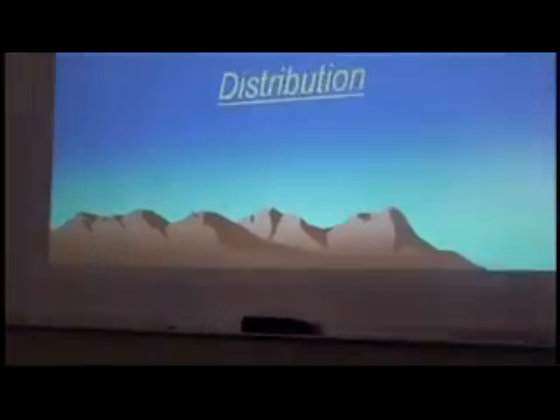This is the kind of damage they find — here's a combustor basket with the unit shut down. This is what they discovered: the metal had started getting damaged, and there's a crack they found. This was a routine inspection, but they discovered that part needed to be replaced. That's why we take the outage, in the spring and fall when we don't use nearly as much power. It's all scheduled through the California ISO.